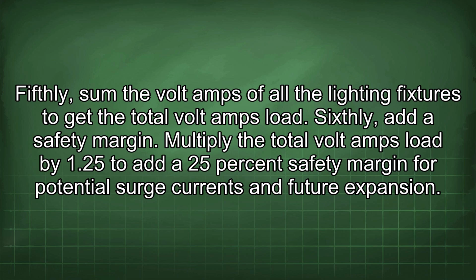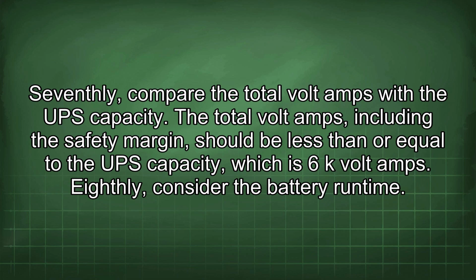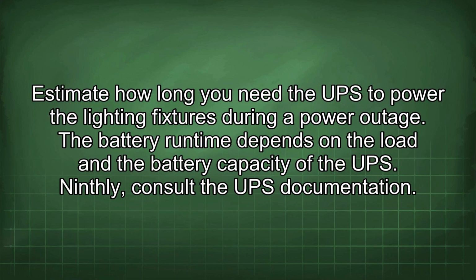Fifthly, sum the volt-amps of all the lighting fixtures to get the total volt-amps load. Sixthly, add a safety margin. Multiply the total volt-amps load by 1.25 to add a 25% safety margin for potential surge currents and future expansion. Seventhly, compare the total volt-amps with the UPS capacity. The total volt-amps, including the safety margin, should be less than or equal to the UPS capacity, which is 6 kVA. Eighthly, consider the battery runtime. Estimate how long you need the UPS to power the lighting fixtures during a power outage. The battery runtime depends on the load and the battery capacity of the UPS.